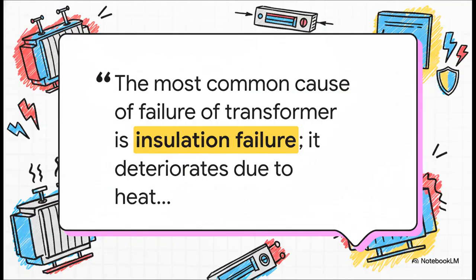But what's the real villain here? The root cause of all this? Well, in so many cases, it all comes down to one thing: insulation failure. You can think of the insulation as the transformer's immune system, and once that system gets compromised by heat, moisture, or just old age, a catastrophic short circuit is pretty much inevitable.